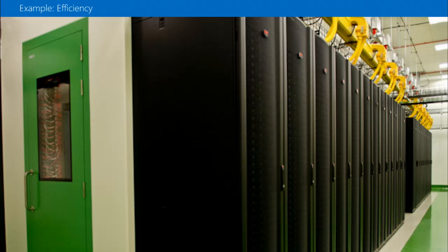The air flows out in the cold aisles, or essentially the outside air aisles outside of the data center. The servers pull that air through, and you can see these two sets of racks are kind of sealed and they have a door on them. And that's to control the airflow. That middle area is actually a lower pressure area, so that the cold air is pulled through the data center by the pressure difference, and then as it heats, it gets pulled out the top and circulated that way. So we get a lot of those same efficiencies that we get in the containerized computing, just in a more traditional co-located facility as well.